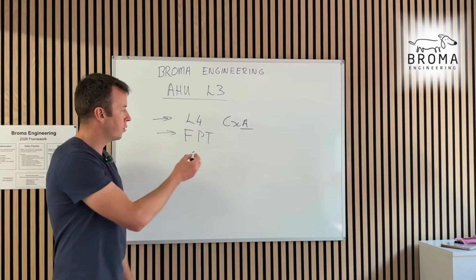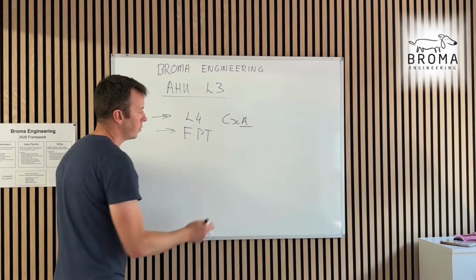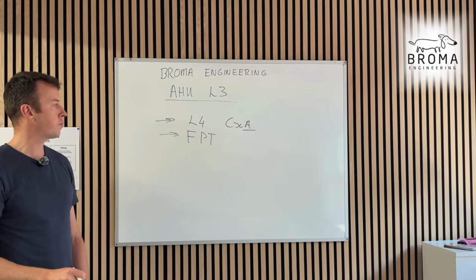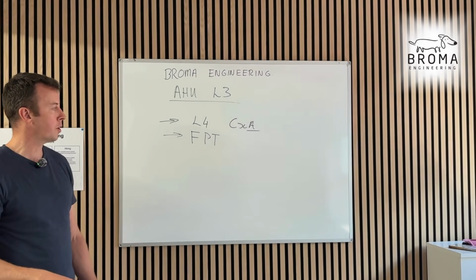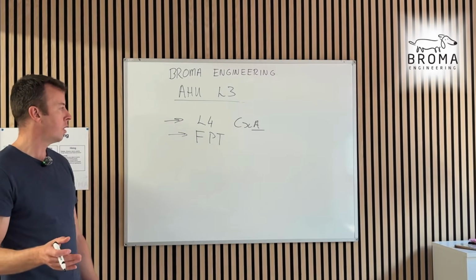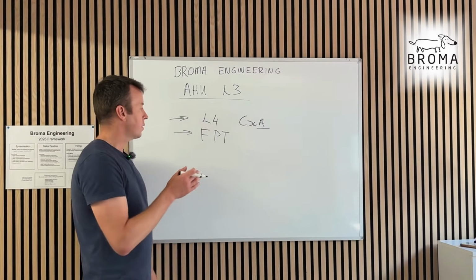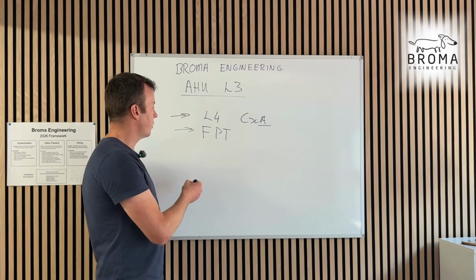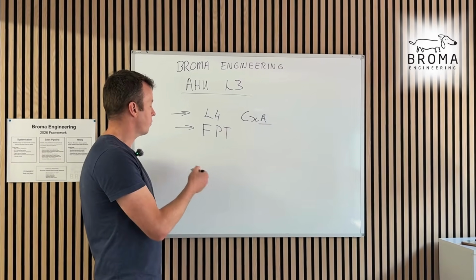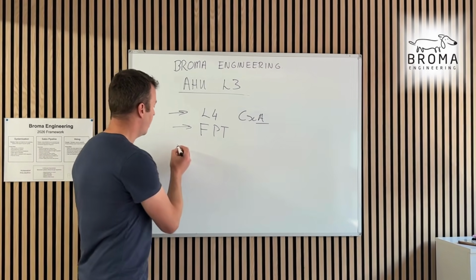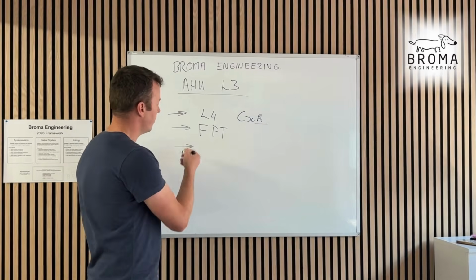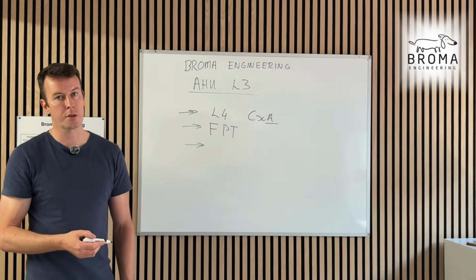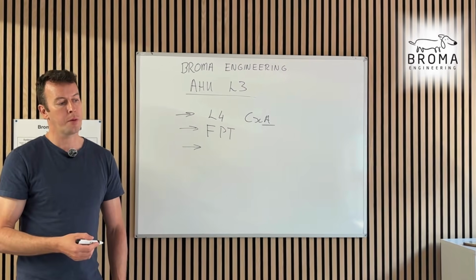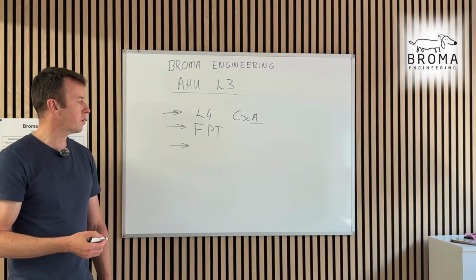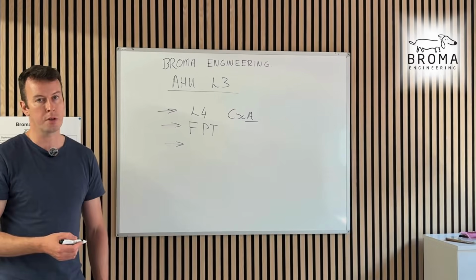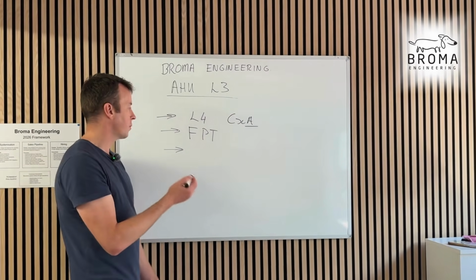The CXA will usually be there for the end of level 2 as well, so they are there for QA/QC - what some people call QA/QC, what some people call commissioning level 2. And then they'll have their specialists come in to run their mechanical scripts, some of them being in AHU. Once level 4 is complete, they will find some snags always. The BMS team will be there to fix certain things, the vendor will be there to fix certain things if needed. Sometimes there's no problems, sometimes there's a few problems.